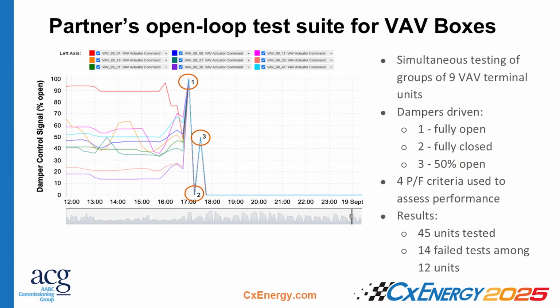So we had a partner that did this in parallel with us in a few of their VAV terminal units in one of their buildings. They drove the damper fully open, then fully closed, then 50% open. For each of these, they had pass-fail criteria, which I'll talk a little bit about in the next slide. They were able to do this with a total of 45 units.